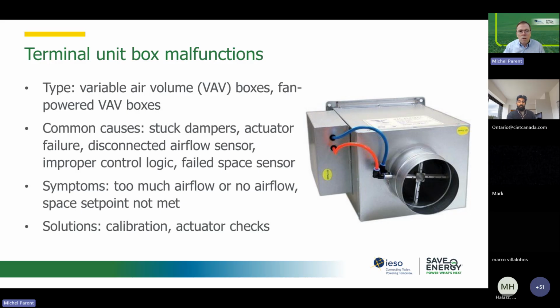The more common failures will obviously be an actuator failure, or it could be one of those old plastic tubes that failed, that disconnected, or that has an air leak, and you no longer get the proper flow measurement from that VAV box, which will result in airflow issues in the zone, people being either too cold or too hot. That's when you will need to have a tool, and I'll show you a tool that we will provide you that can help you, and unfortunately it's just for one type of system.